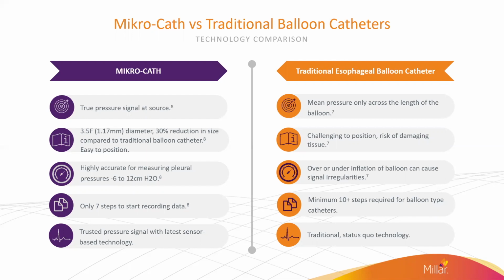When comparing the Millar Mikro-Cath to traditional esophageal balloon pressure catheters, the 30% smaller diameter design allows for increased patient comfort and reduced risk of tissue damage when inserting and positioning the device. The Mikro-Cath also features the latest sensor-based technology mounted at the tip for highly accurate true pressure signals at the site of sensor placement. This differs from traditional esophageal pressure catheters where only a mean pressure is calculated along the length of the inflated balloon.